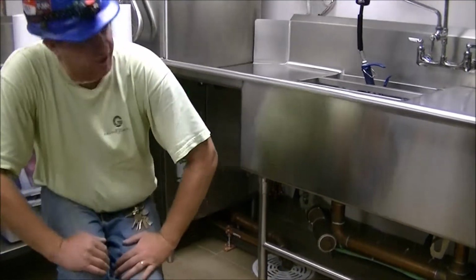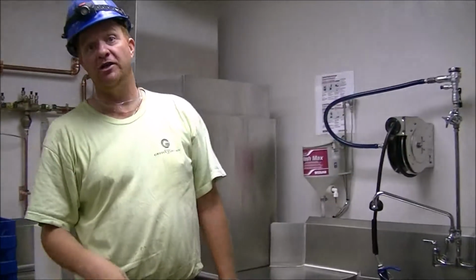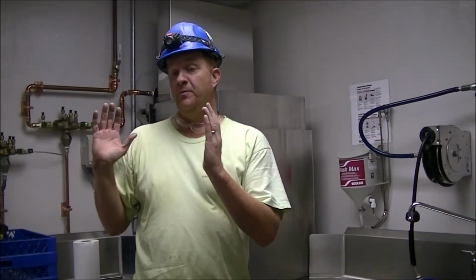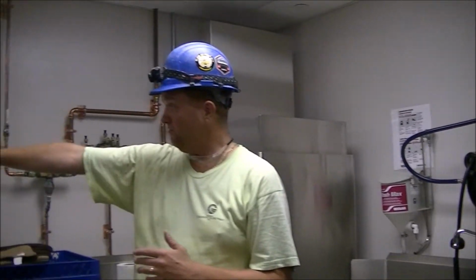There's also another section getting heat trace, right by the main panel where we first started, about 10 feet of pipe up there. That's the waste for this sink over there, so it'll get heat trace too, again just to keep the flow of grease going. It's very maintenance free, you just switch it on and let it run, and it'll last forever.